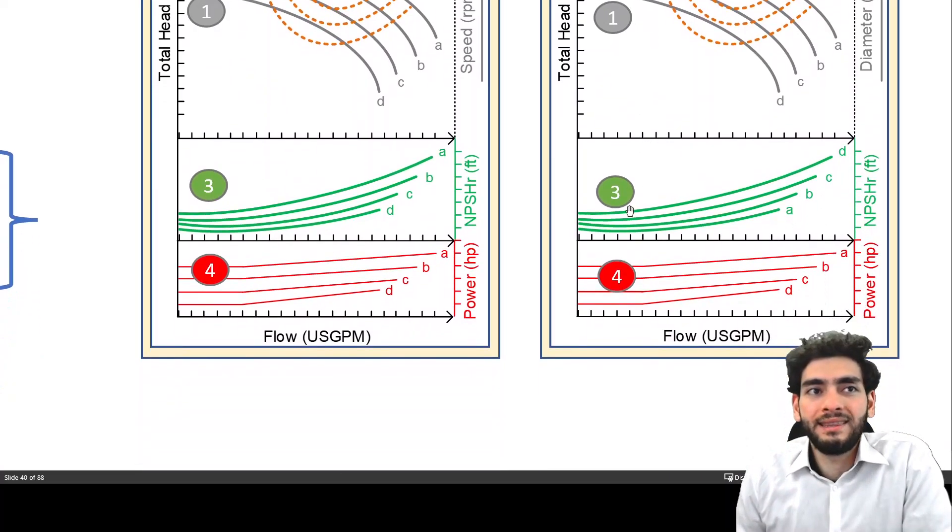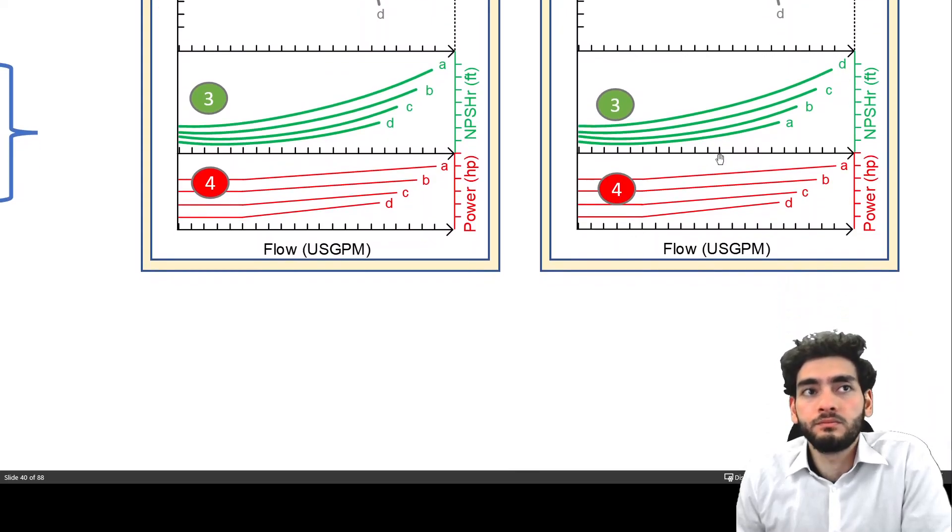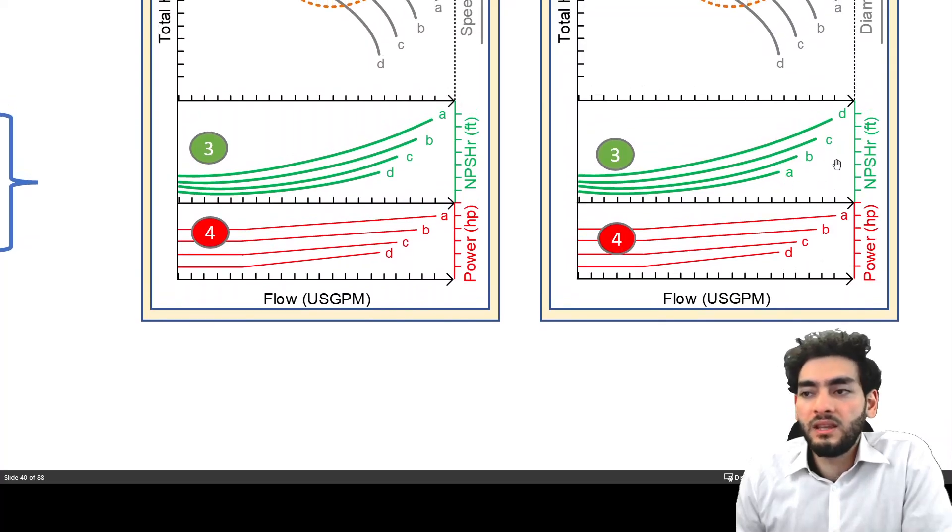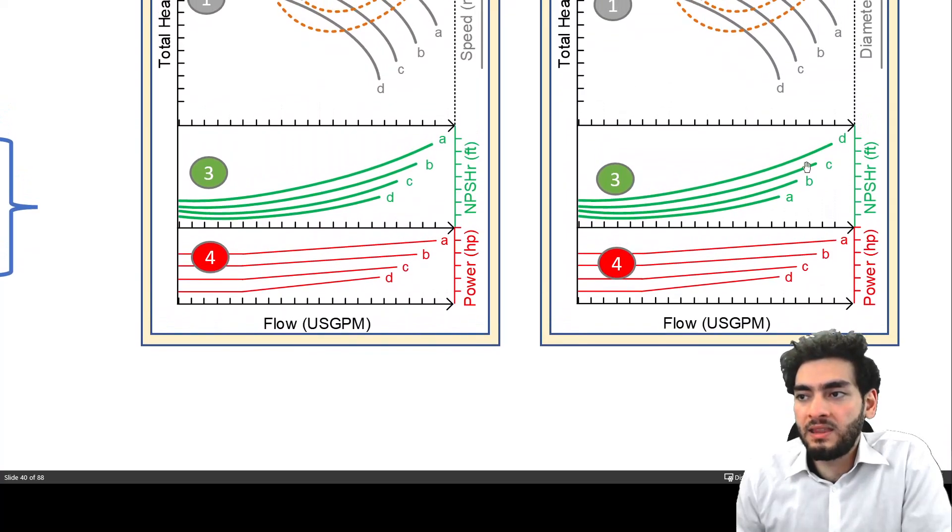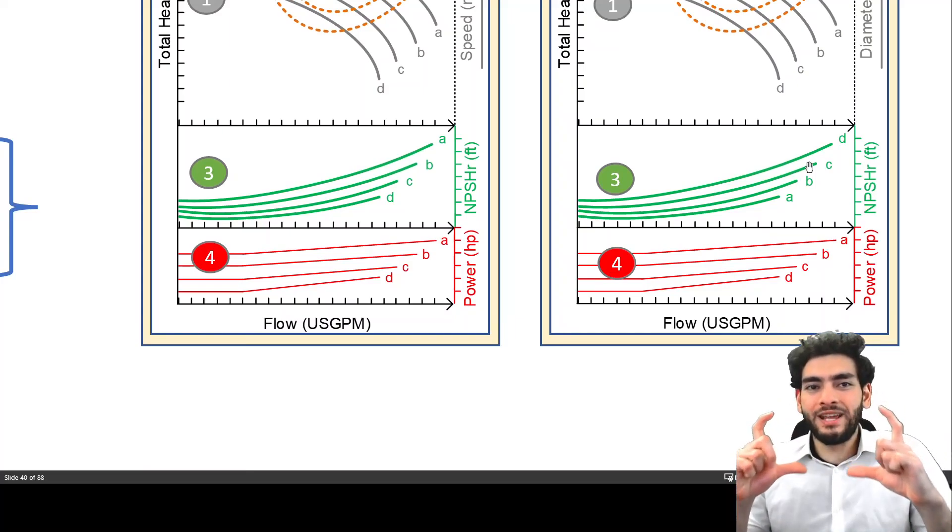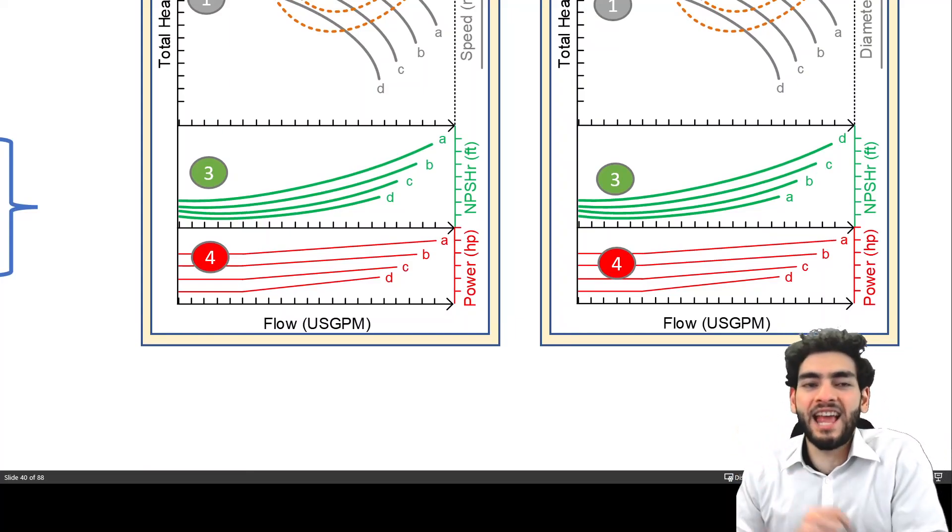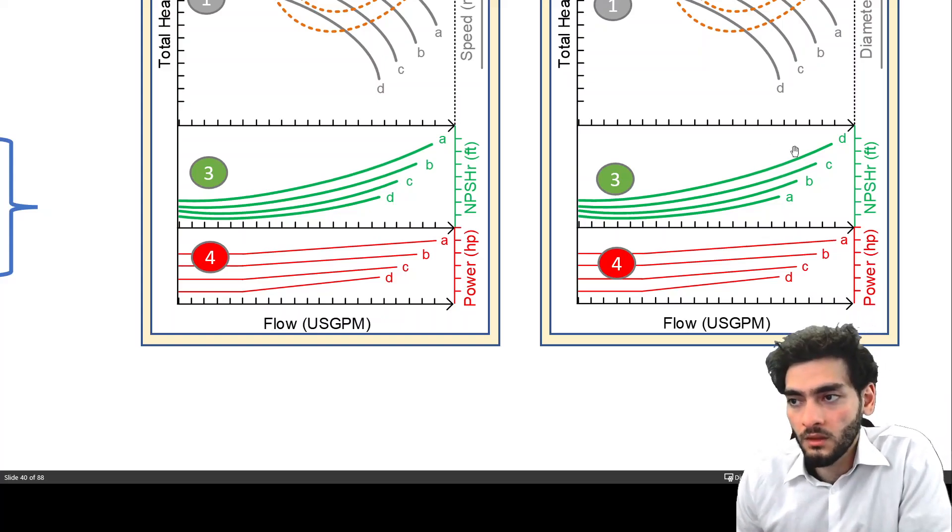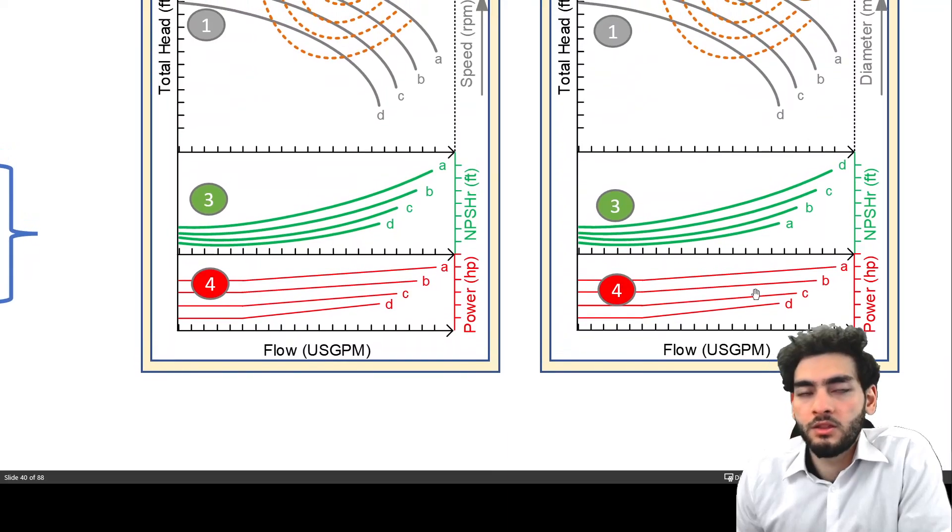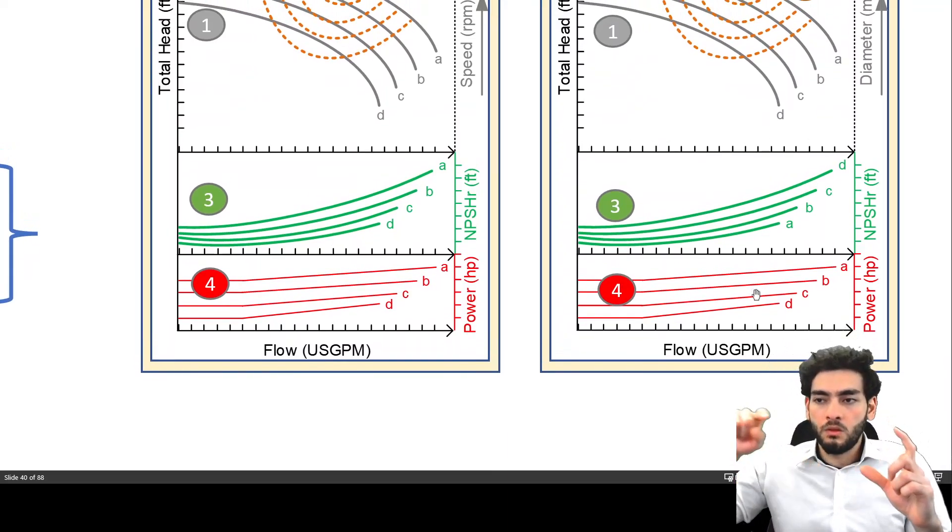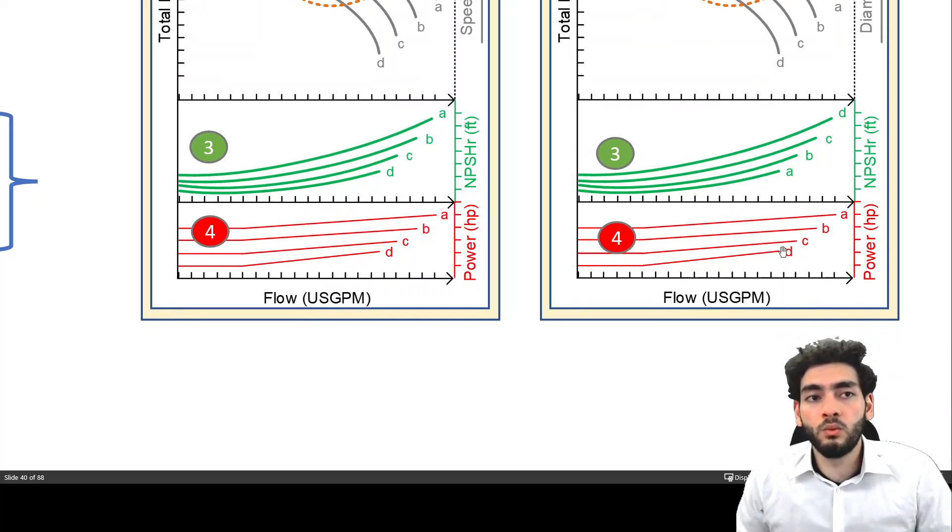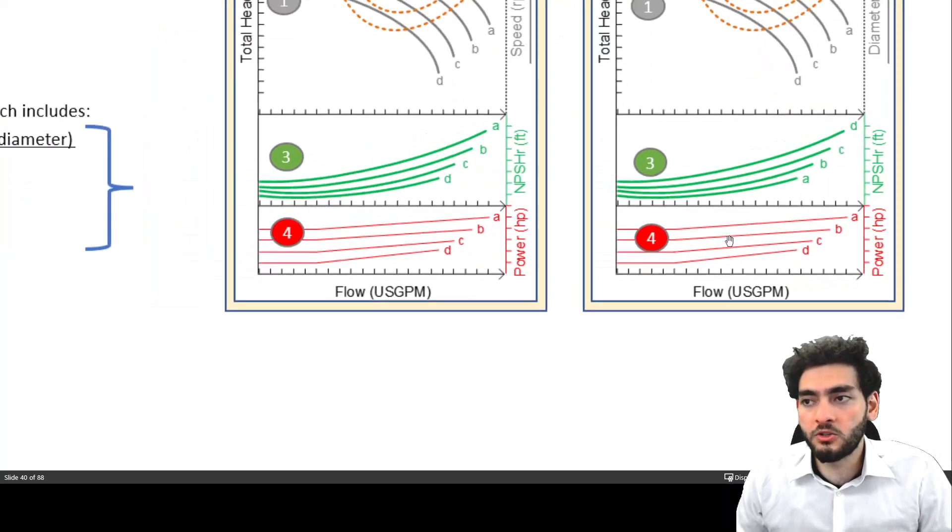And if we look at the NPSHR curves, now this trend is that the bigger the impeller is, the less NPSHR required for the pump. And however, the bigger the impeller, the more force you'll be providing the fluid, then the more power the pump will require for this particular operation.